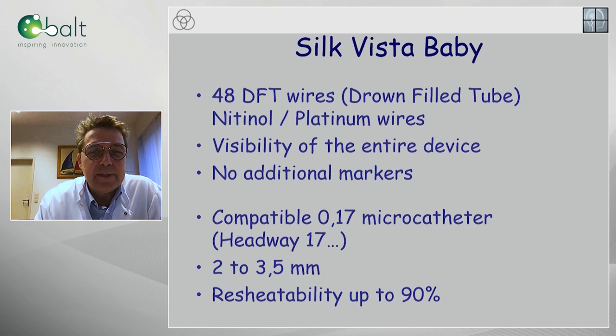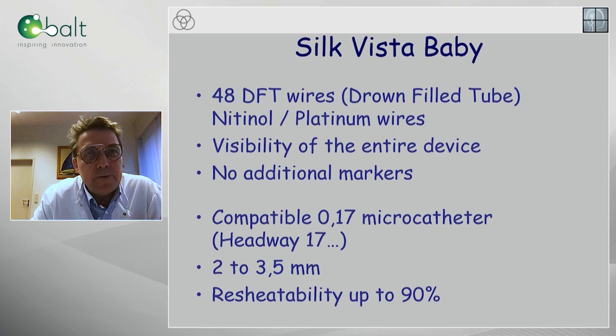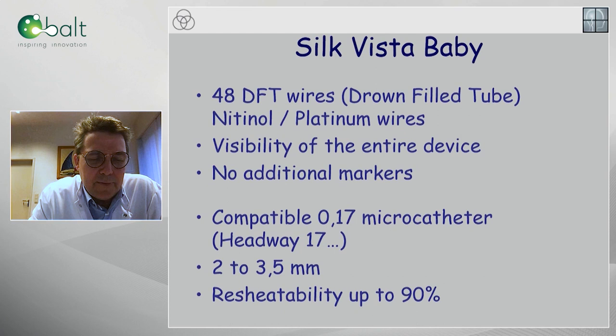The stent first came out as the Silk Vista in small size, called the baby, with 48 wires made of DFT — drawn filled tube — wires, which means that each of those wires is visible, making the whole device entirely visible without the need for additional markers. The Vista baby goes through a 17 microcatheter, a catheter with a 0.017 inch lumen — definitely the smallest flow diverter compatible with the smallest microcatheters. Size ranges between 2 and 3.5 millimeters. Another advantage is that it can be resheathed up to 90%.